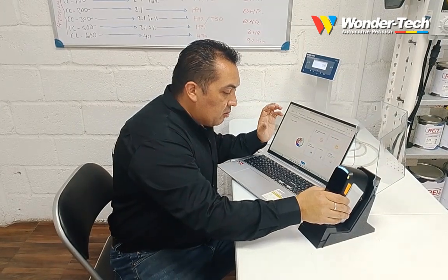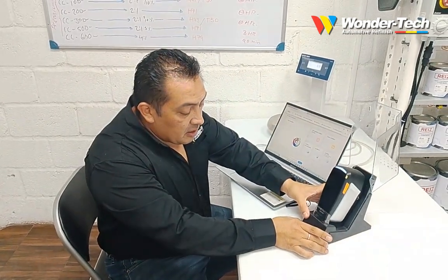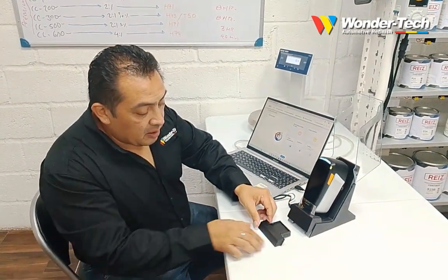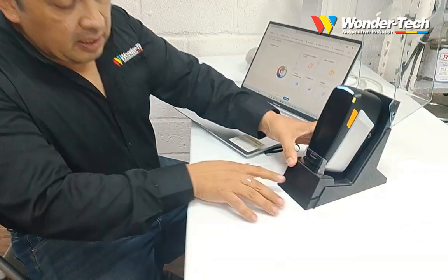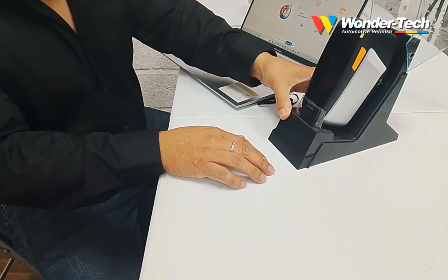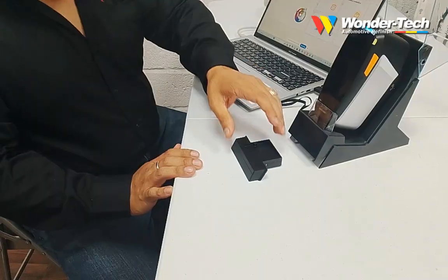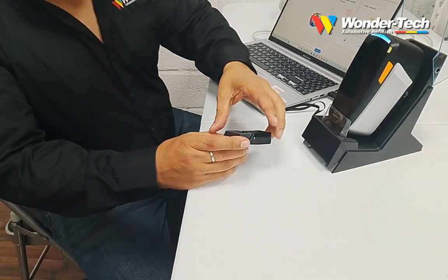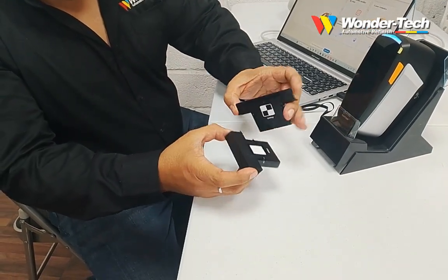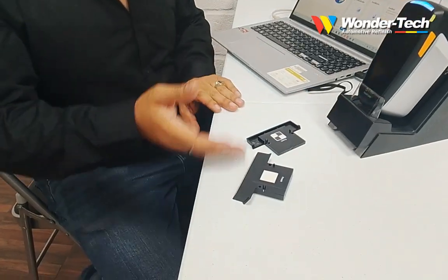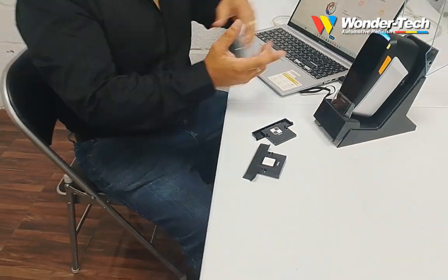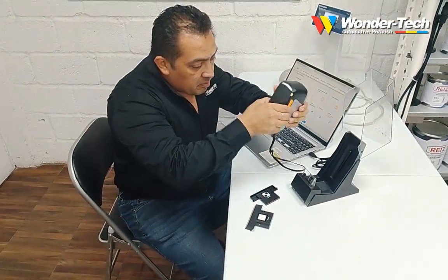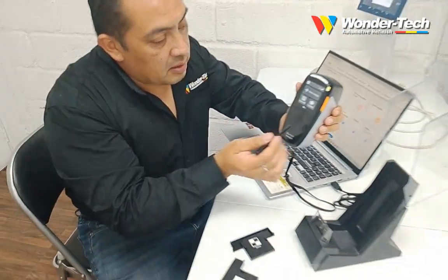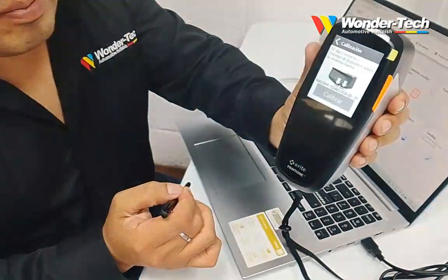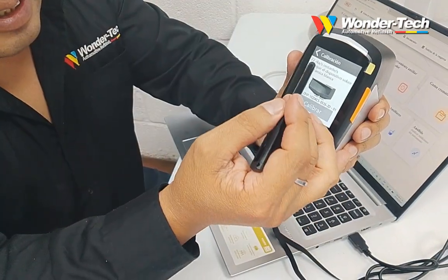On the bottom of the charging dock, you'll find the calibration reference tiles. They're conveniently stored inside the dock itself. At first glance, they almost look like part of the charging station. Remove the calibration standard, and you'll notice there are 2 ceramic reference tiles, a solid white tile, a white and black calibration tile. To begin the calibration process, simply select Calibrate.